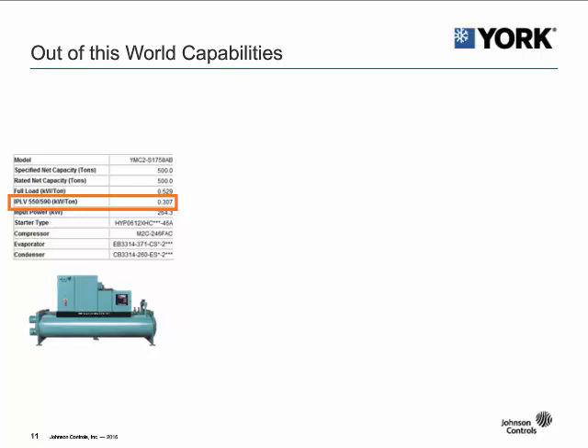If it's the opposite, if I go from 44 degrees to 45, your chiller is going to become more efficient by 2 to 2.5%. And again, we get back to what makes up lift is that leaving temperature on both shells, the evaporator and condenser. So to talk about 38 to 37 degrees leaving evaporator, it will have a negative impact on your chiller efficiency. So it will just have to be something that is taken account of if you want to start to make ice for thermal storage.